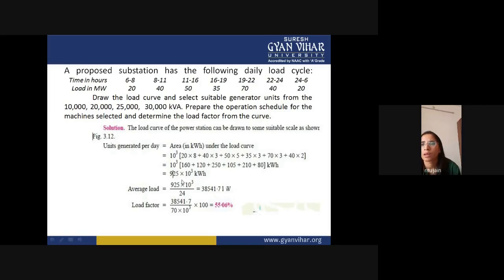Okay. Now we next come to this point: what is your average load? Average load can be calculated by dividing the units by 24 hours of a day. So you can easily calculate the average load. Next, load factor. The formula of load factor, I have already told you, is average load upon maximum demand.